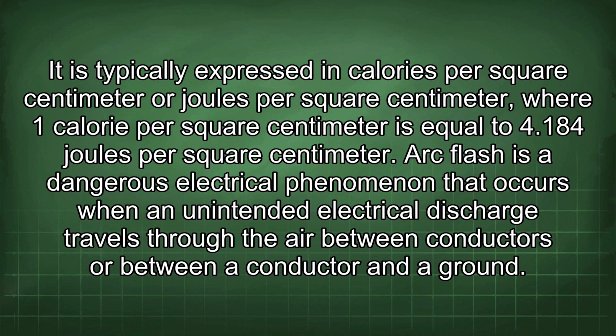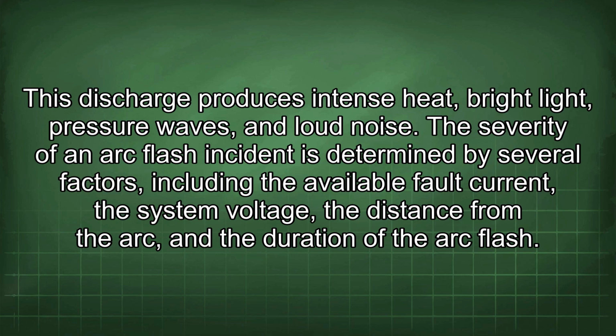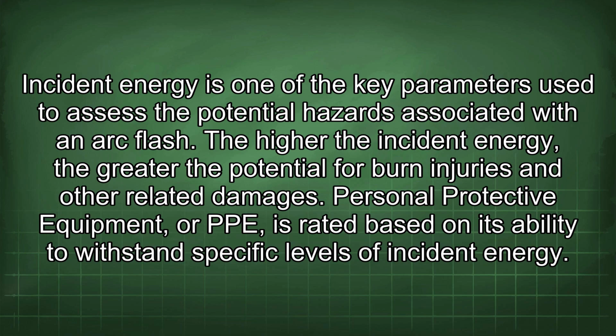Arc flash is a dangerous electrical phenomenon that occurs when an unintended electrical discharge travels through the air between conductors or between a conductor and a ground. This discharge produces intense heat, bright light, pressure waves, and loud noise. The severity of an arc flash incident is determined by several factors, including the available fault current, the system voltage, the distance from the arc, and the duration of the arc flash. Incident energy is one of the key parameters used to assess the potential hazards associated with an arc flash. The higher the incident energy, the greater the potential for burn injuries and other related damages.